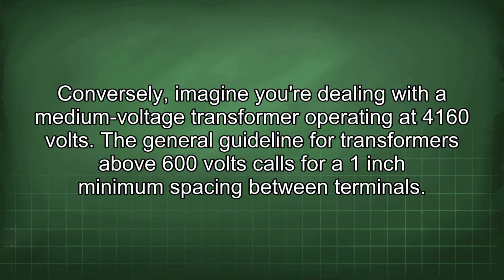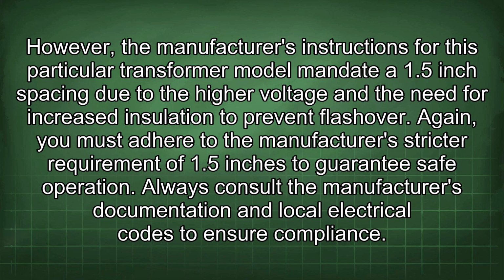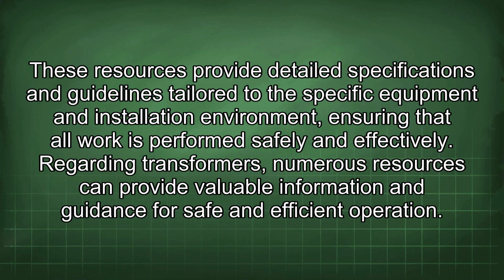Conversely, imagine you're dealing with a medium voltage transformer operating at 4160 volts. The general guideline for transformers above 600 volts calls for a 1 inch minimum spacing between terminals. However, the manufacturer's instructions for this particular transformer model mandate a 1.5 inch spacing due to the higher voltage and the need for increased insulation to prevent flashover. Again, you must adhere to the manufacturer's stricter requirement of 1.5 inches to guarantee safe operation. Always consult the manufacturer's documentation and local electrical codes to ensure compliance.